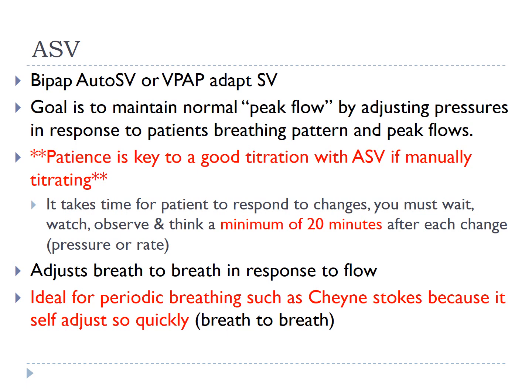These machines measure the peak flow of the last 4 breaths. It tries to increase pressure support by adjusting the IPAP and EPAP pressures in order to maintain the peak flow of the last 4 breaths. So the pressures automatically change rather quickly, and we're watching for the patient's response to those pressure changes. As the patient takes its 5th breath, the first of the 4 breaths drops off, and then the machine adjusts to the last 4 breaths. So it's constantly re-averaging the peak flows and then adjusting to the patient. So it's adjusting rather quickly. You just don't see it.